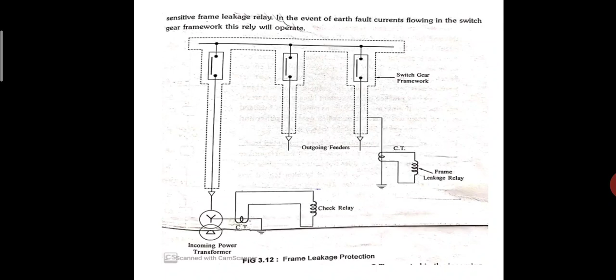The check relay is an earth fault relay energized from a CT mounted in the incoming transformer neutral earth connection. The contacts of the check relay and the frame earth leakage relay are in series, so that two independent relays must operate before the trip circuit is completed.